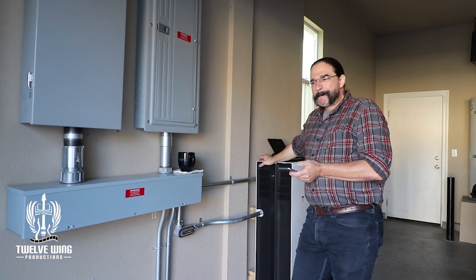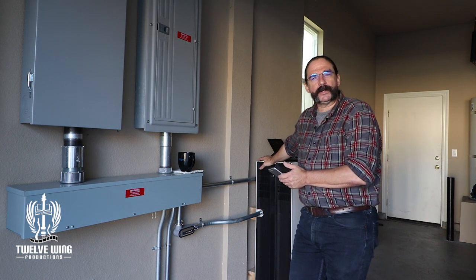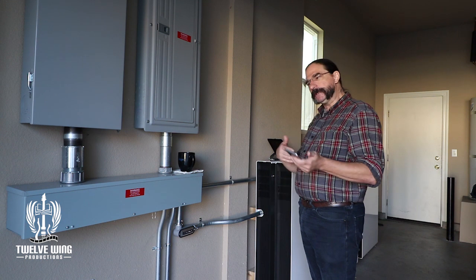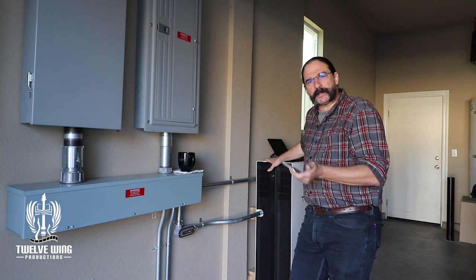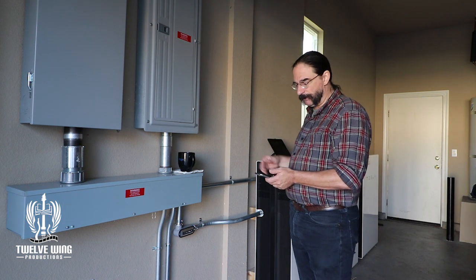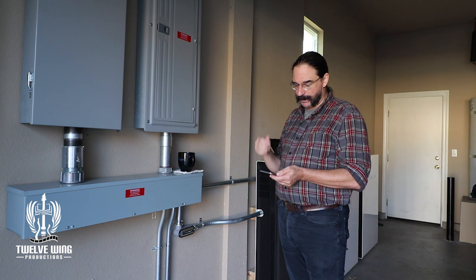Okay, welcome back. It's a little over an hour later and the system is still recognizing all six Powerwall batteries, at least as far as the app is concerned. So now we're watching the physical reality of what happens to the charge. When we started, the batteries were at 20% — 16.4 kilowatt hours. Now we're up to about 21%. We've shut off those two Powerwalls, so the reduction of two should leave us around 54.6 kilowatt hours total, based on the 82 kilowatt hours we know we have, minus the two supposedly shut off. The Tesla gateway gives us access to that information, which is very handy.